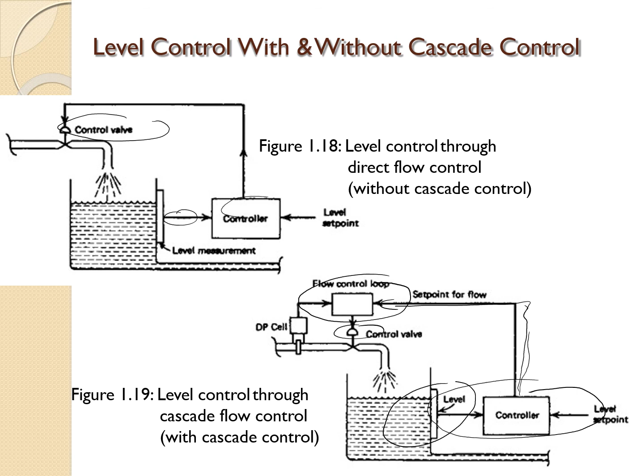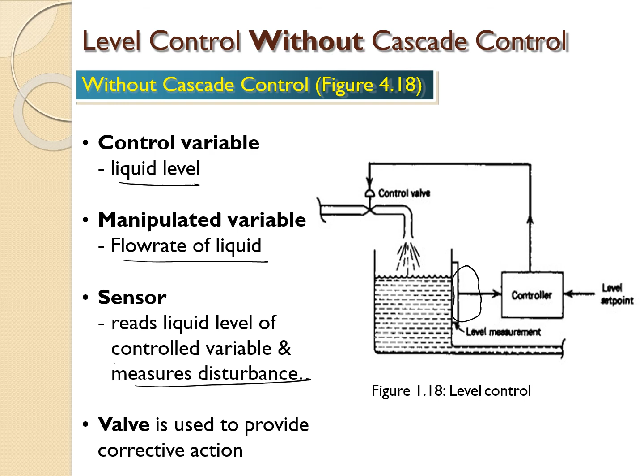So, level control without cascade control. The control variable is liquid level. The manipulated variable is the flow rate of the liquid. The sensor in here measures the liquid level, the control variable, and also the measured disturbance. So we read the level of the control variable here and also the measured disturbance. The valve is used to provide the corrective action.